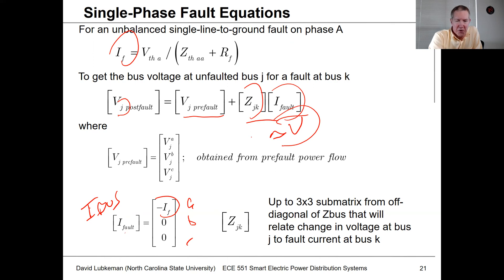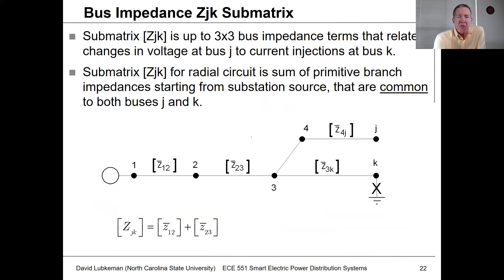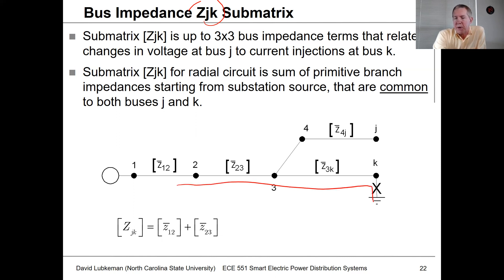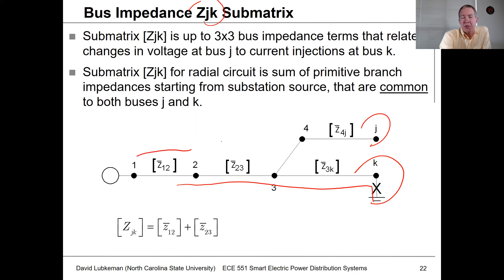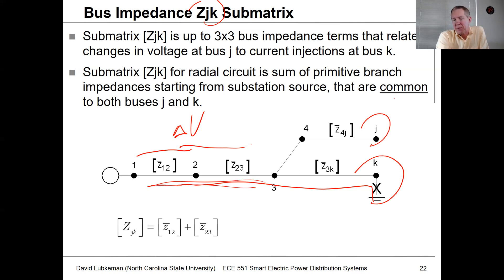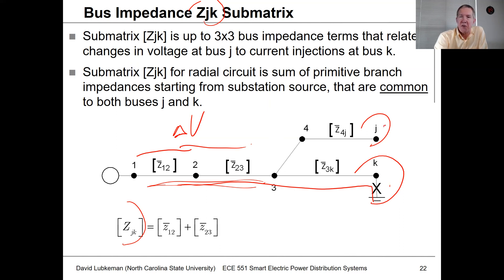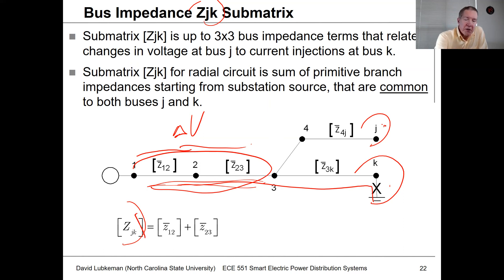We'll see this later in the examples with numbers as well. The value Z_JK is the impedance that's common to both buses. Suppose the fault is at bus K — how is that going to impact the voltage at bus J? It's going to impact the voltage due to the change in voltage occurring across these two sections, which in this case is Z_12 plus Z_23. One way you can get Z_JK is just through inspection: look at the fault bus K and the non-fault bus J, identify the sections of the circuit common to both, and simply sum those up.